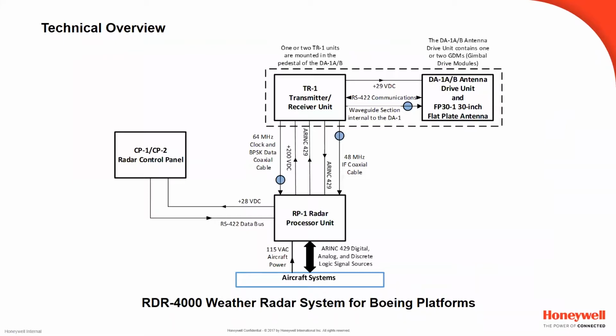Sometimes a question will come up: why such a high voltage between the RP1 and the TR1, the plus 200 volts? It's because we really don't want to provide a voltage like 28 volts DC at several amps. Much like the electric companies, if you have a much higher voltage and a lower current, you still have the same power, the wattage capability. And so it's just easier on the wiring to use a higher voltage with a lower current. And then later on, you can do a down conversion of the voltage and achieve the currents necessary at the same time.